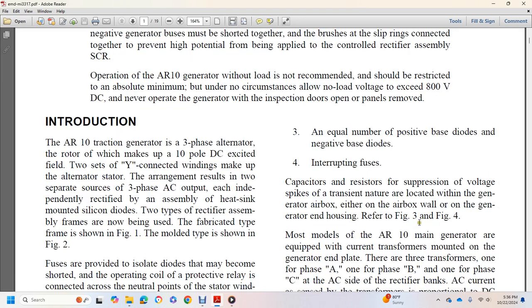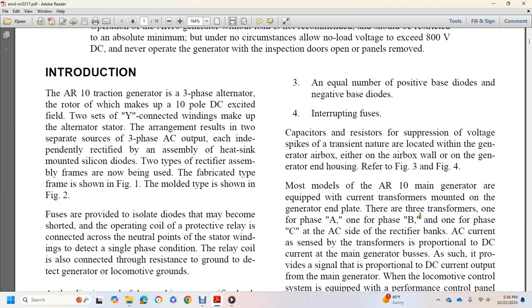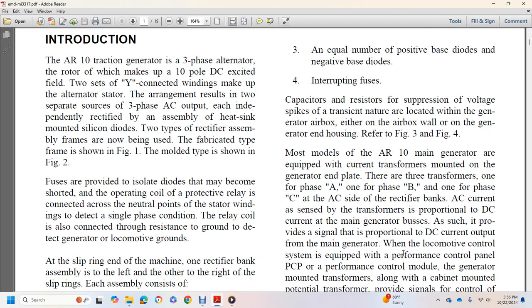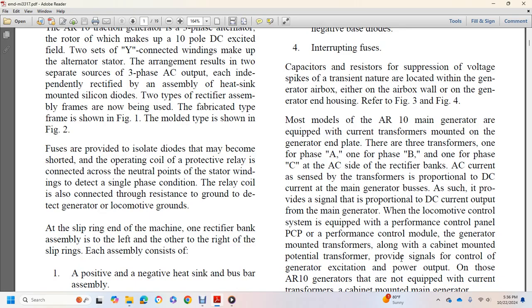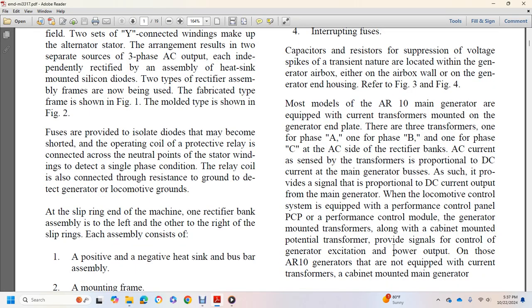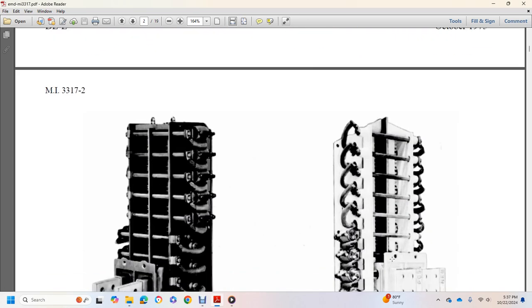Refer to figures 3 and 4. Most models of the AR10 main generator are equipped with current transformers mounted on the generator end plate, three transformers: phase A, phase B, and phase C. With an AC rectifier bank, the transformer provides proportional DC current from the main generator as a signal output to the main channel of the locomotive control system, equipped with the performance control panel, the PCP, and performance control module. The generator-mounted transformer, along with the cabinet-mounted potential transformer, provides the signal for control of generator excitation and power output. Some AR10 generators are not equipped with the current transformer and cab-mounted main generator.